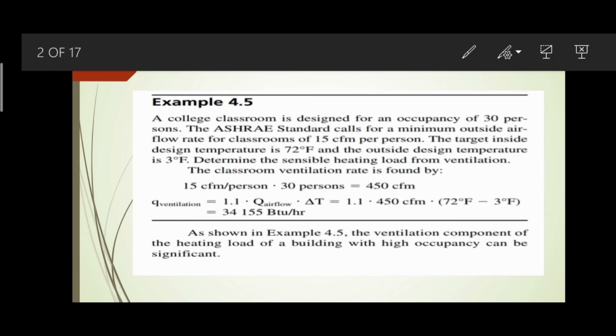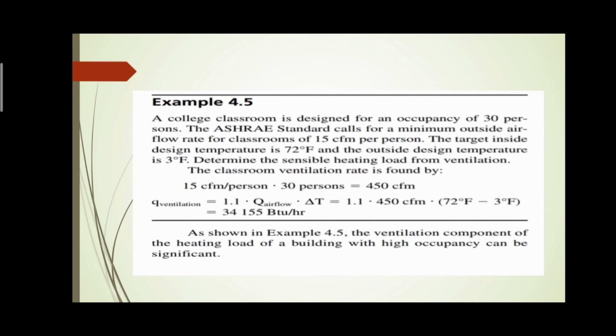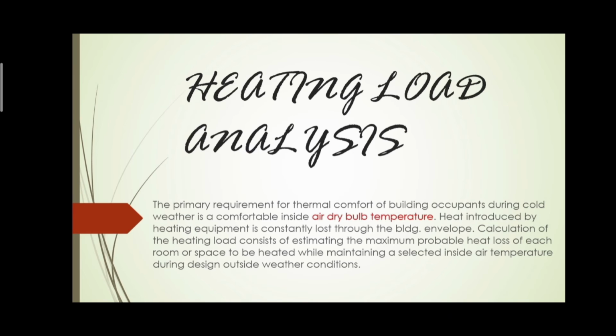Tapos, ta-times din natin doon yung delta T, which is the inside design temperature minus the outside design temperature. So, ang total nun is 34,155 BTU per hour. So, as shown in example 4.5, the ventilation component of the heating load of a building with high occupancy can be significant.